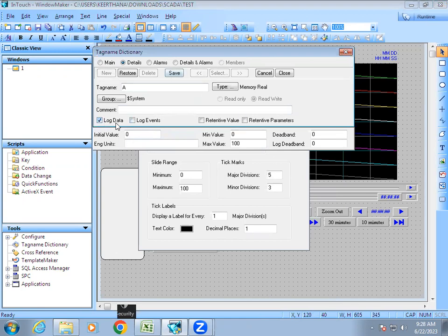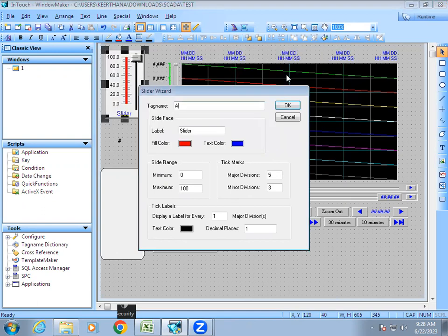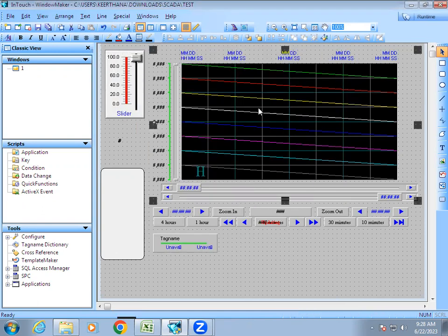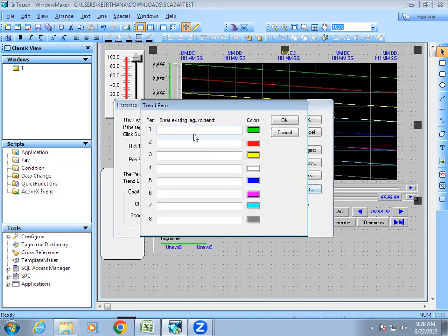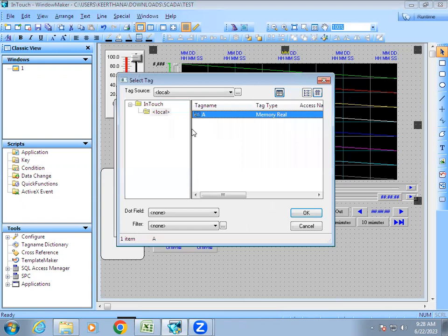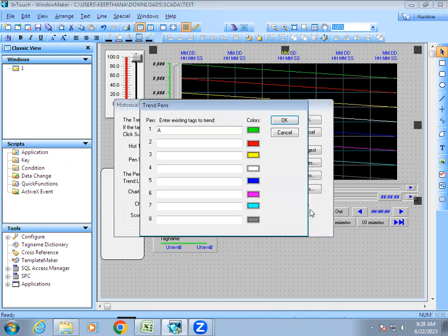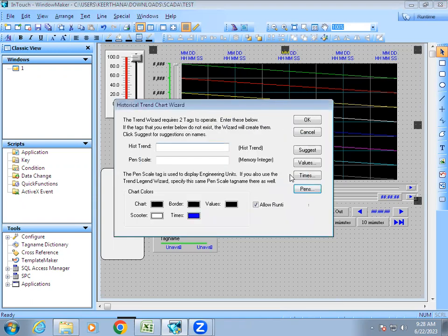By enabling Log Data, the historian file will store the past data and the graph will be able to display it. Once Log Data is enabled, if you double-click the chart and go to Pens and double-click there, it will now display your tag name. Select it and give OK.